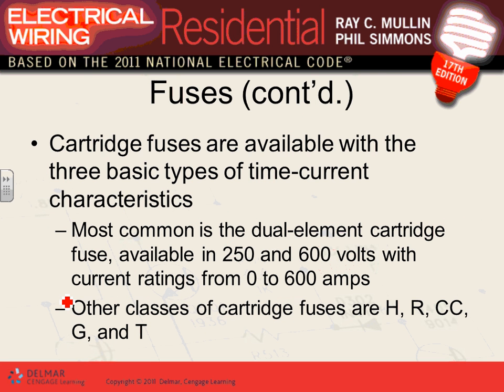When you were sizing fuses for motors: if it's a non-time-delay fuse, you use 300% for motors. For dual-element time-delay fuses, you use 175%.